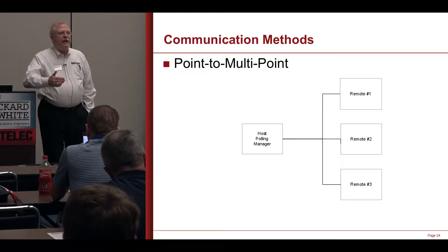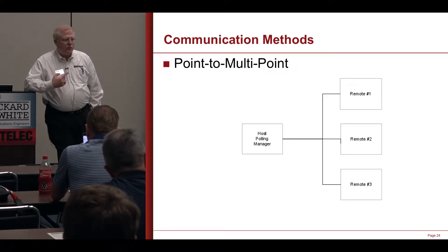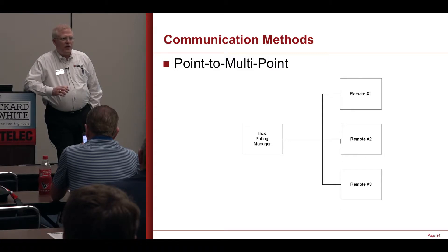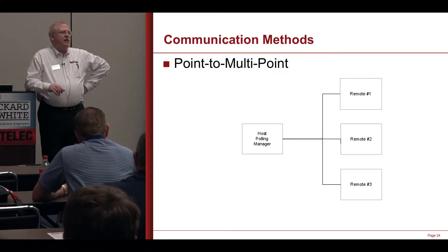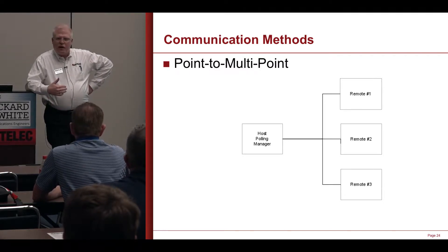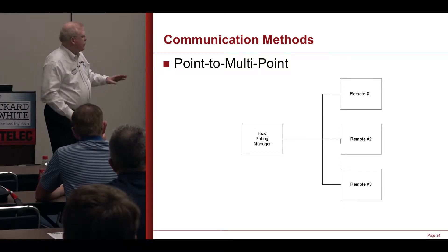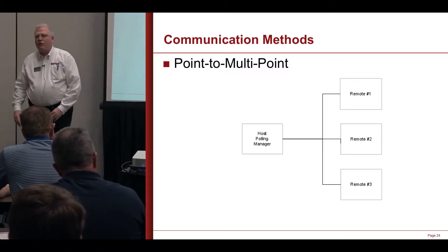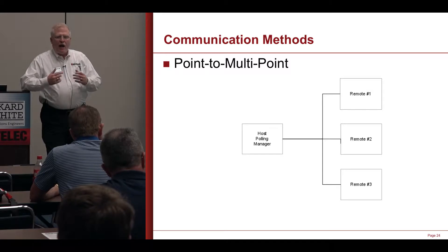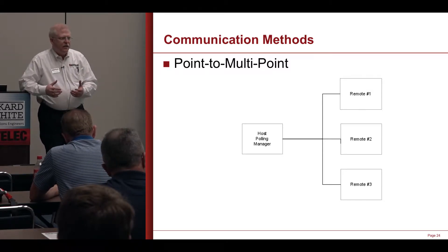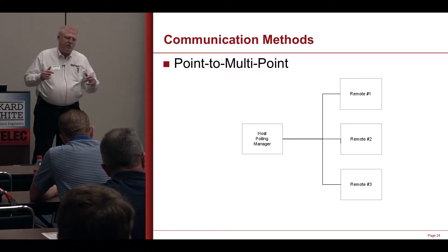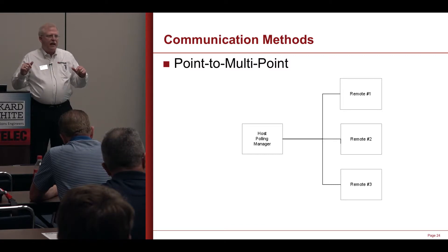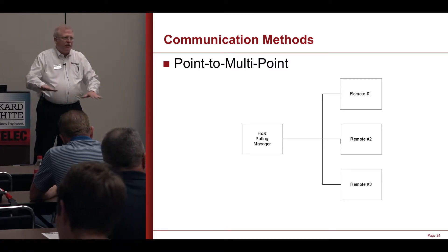From a radio analogy, what's the analogy to point-to-multipoint? What happens in a radio network when we key up the mic and we want to talk to one radio that's a slave behind the master? Everybody hears what's broadcast, and only the guy who's addressed answers back. Most of the radio systems out there are point-to-multipoint systems. Even some of the newer IP systems — all that means is they support that kind of addressing, they're still point-to-multipoint. Everybody behind the master hears when the broadcast is made. Even mesh-type networks are just distributing the master around, but at the bottom level they're all still point-to-multipoint.